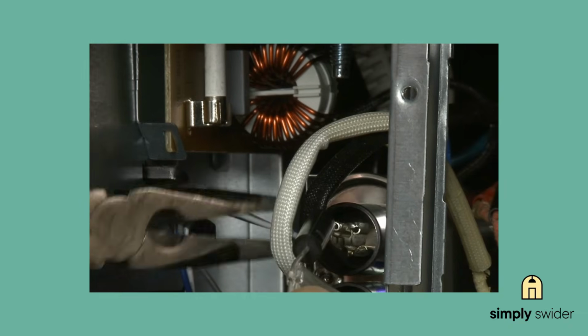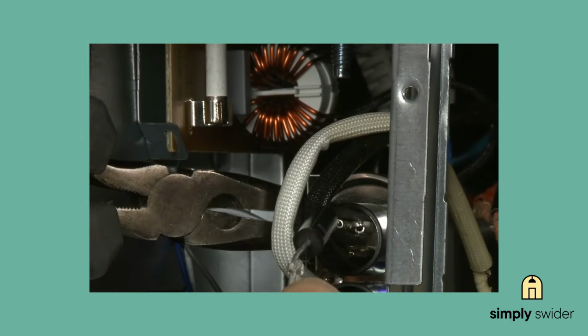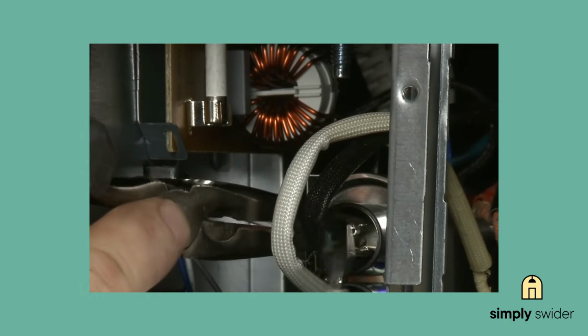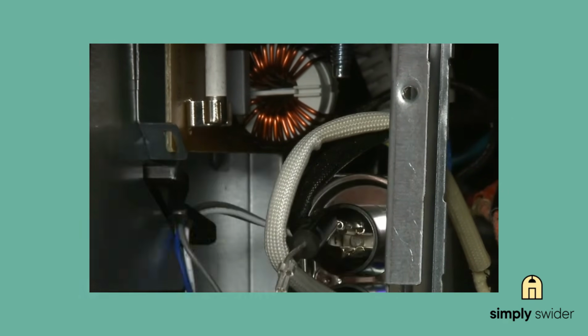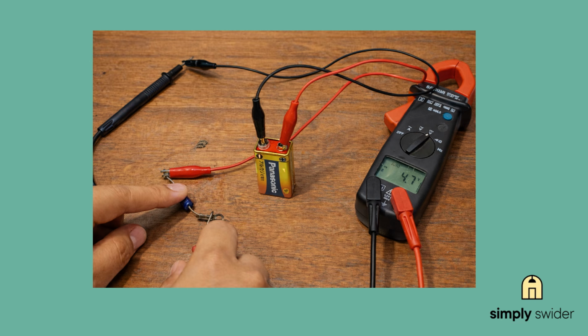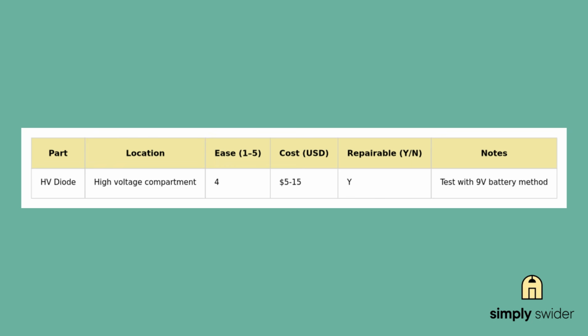Testing HV diodes is a little different than regular diodes. Most standard multimeters can't handle the voltage, so you need to do what's called a 9-volt battery test. You connect the diode in series with a 9-volt battery and measure the voltage drop. A good diode should only allow current to flow one direction. If you're getting continuity both ways, it's shorted. Good news is these things are cheap, usually 5 to 15 bucks. And since you're already in there with the capacitor work, it's often worth replacing both at the same time.